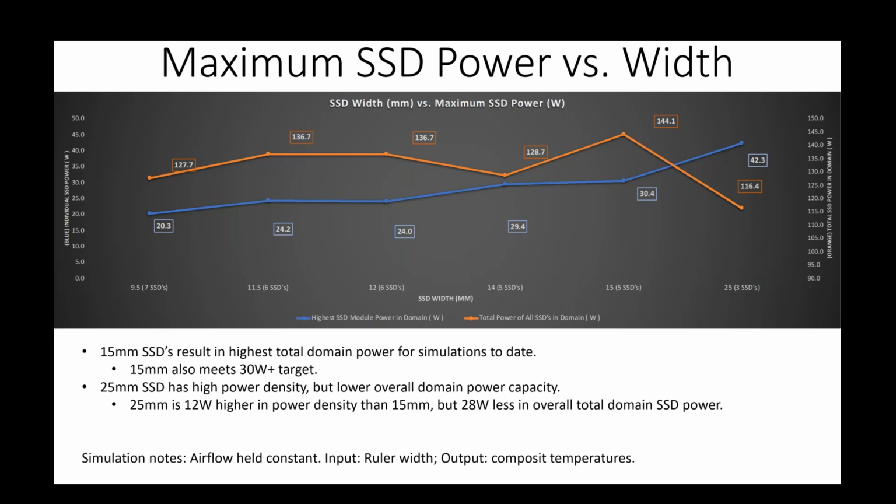No, so the reason why I can't use inlet is because inlet is going to change with your pressure curve, right? And so that's why I'm using through channel velocity as opposed to your inlet velocity. And so even internally, if we engage a supplier, we do give an inlet of a certain airflow velocity. But for our system, that would be different from your system. But the one thing that shouldn't be different is how much heat or how much air or fluid it takes to remove that energy across that drive.